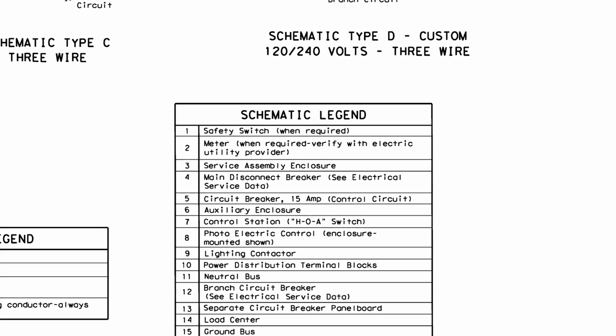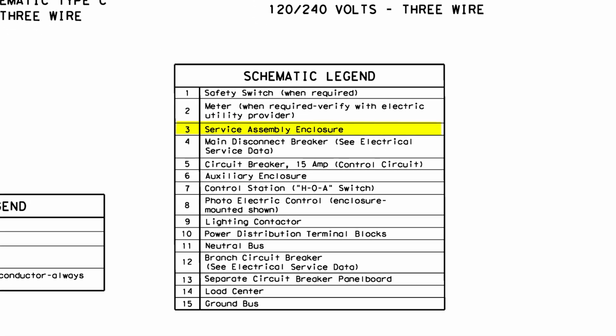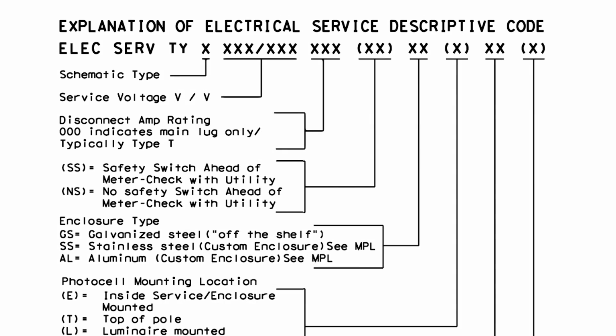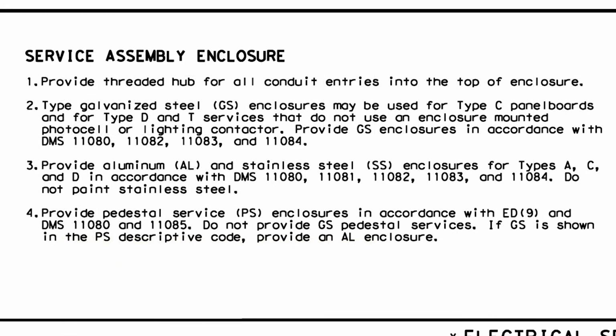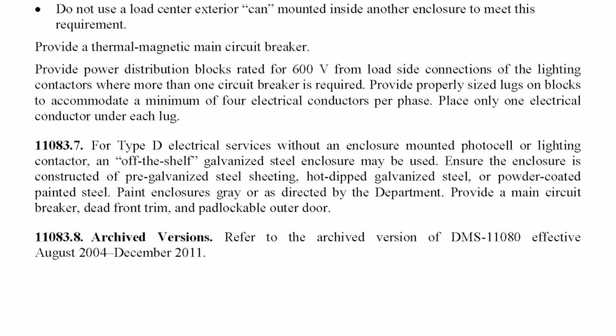The schematic's legend is located on the lower center of ED6. First, we will inspect the service enclosure, noted on the schematic as item number 3. On ED5, the service descriptive code legend shows that this enclosure can be made of either stainless steel or aluminum material. A Type D enclosure can be made of galvanized steel, but only if it is an off-the-shelf type of enclosure. This equipment does not have internal parts, such as a photocell, lighting contactor, and hand-off-auto switch that a custom Type D might have.